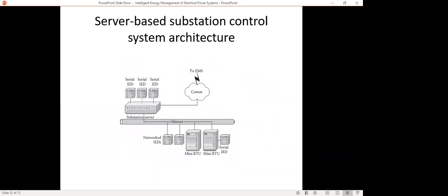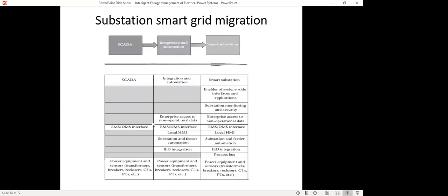Here, after the SCADA, we have a server-based substation control system architecture. As I told you, we have the IED devices. These IED devices send the information to the energy management systems through the communication technologies. Also, through the substation server, we can collect all the information from the serial IEDs, mini RTUs, and from the network IEDs. So here we are integrating the SCADA systems for the smart substations.